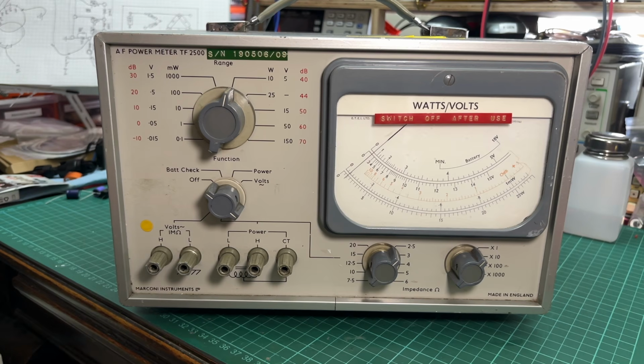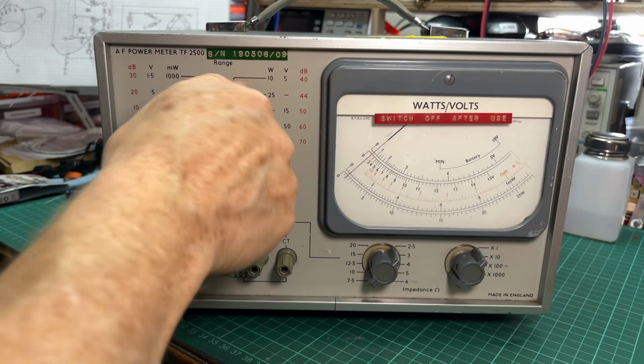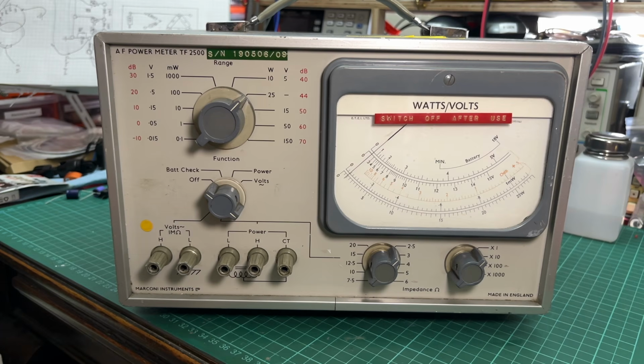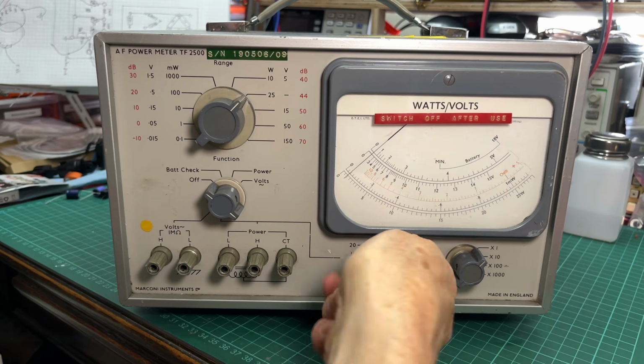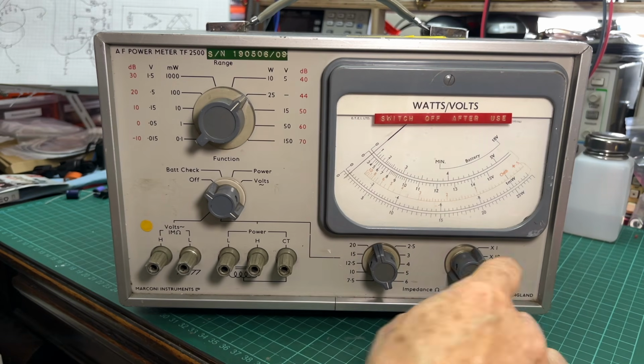It'll also measure a voltage up to 150 volts, and I think that is AC, it is AC, from 10 hertz to 1 megahertz. All of that is done by this switch here, and then the function switch at the front. For power measurement, the amplifier is preceded by a switched input transformer and attenuators, providing 7 power ranges for balanced and unbalanced measurements at any one of 40 input impedances. That's these switches down here, so there's 10 and then a multiplier as well.